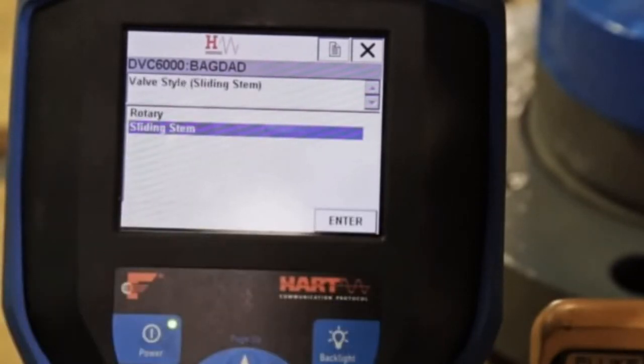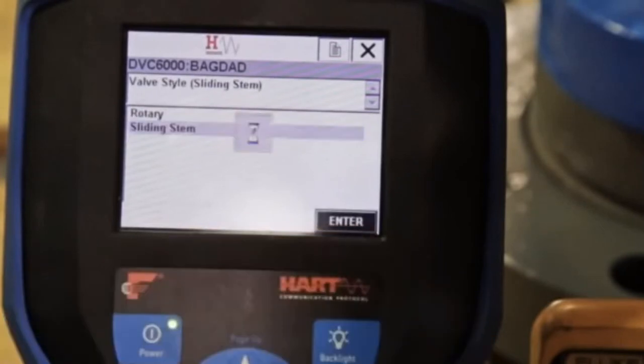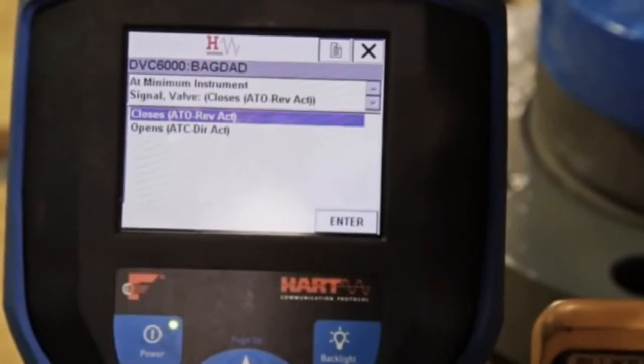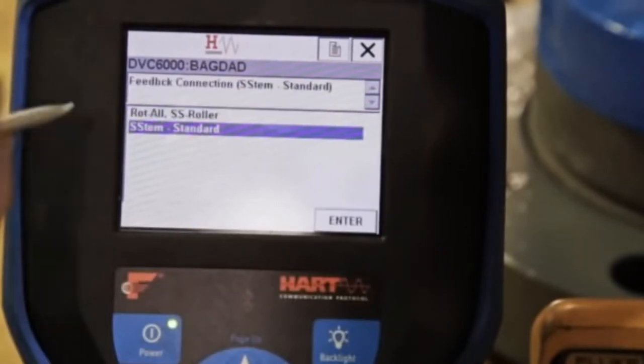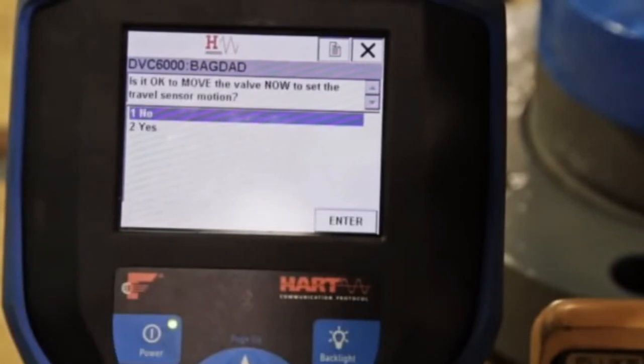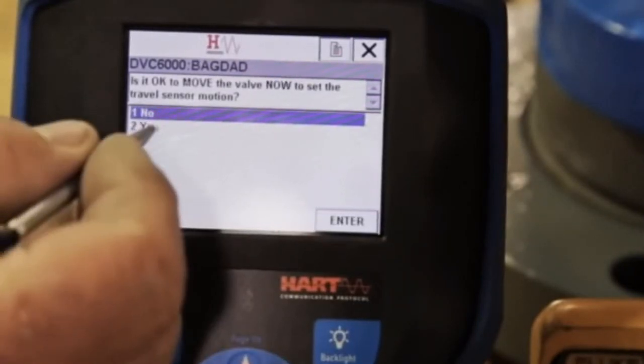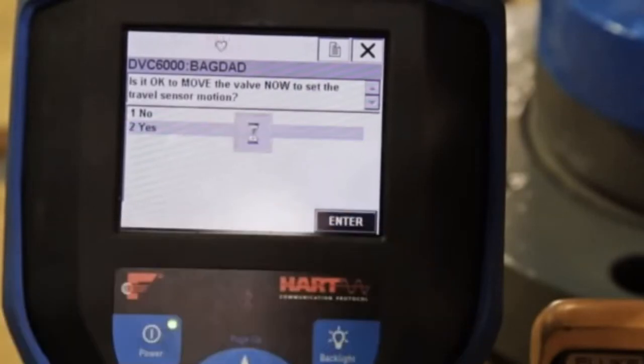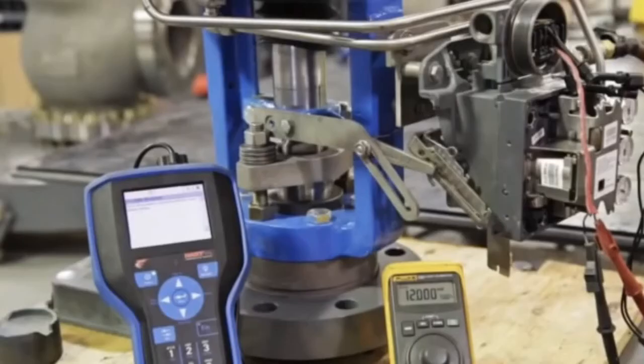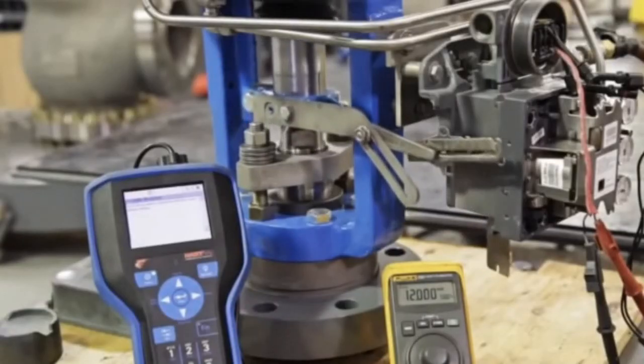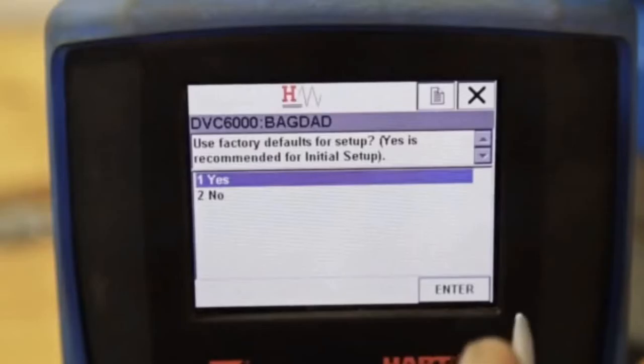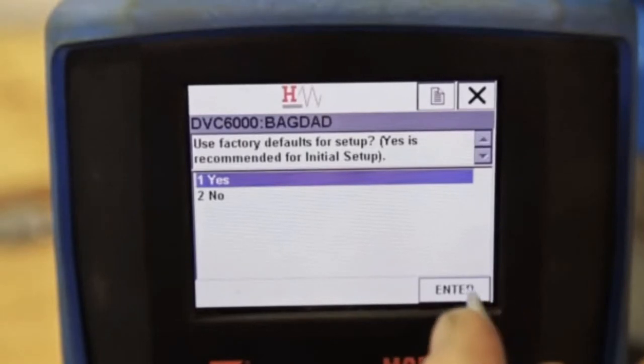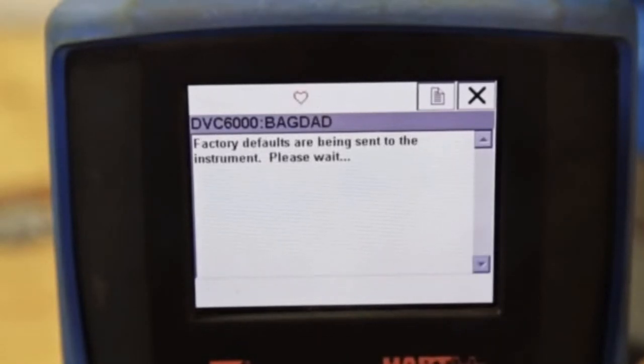This valve is a sliding stem style valve. It also closes at minimum instrument signal, so we'll choose Closes. Sliding stem standard for the feedback connection. Now it will ask if it's okay to move the valve to set the travel sensor motion. Select Yes. The valve should start to move. We will select Yes to use factory tuning defaults for setup.